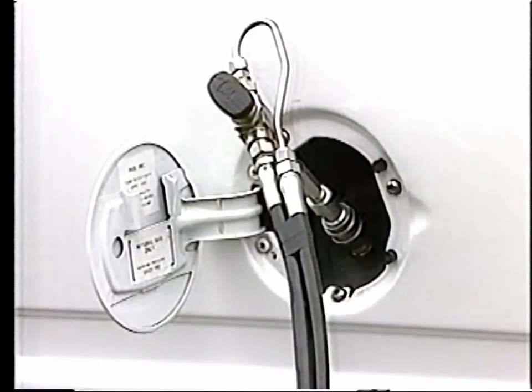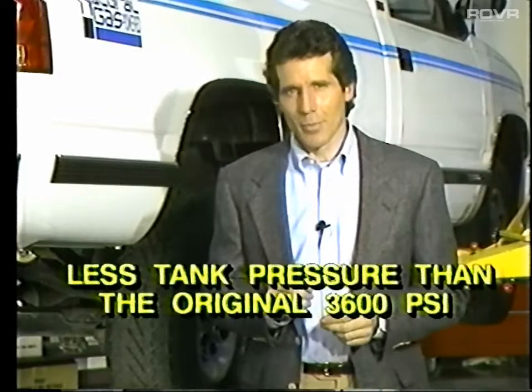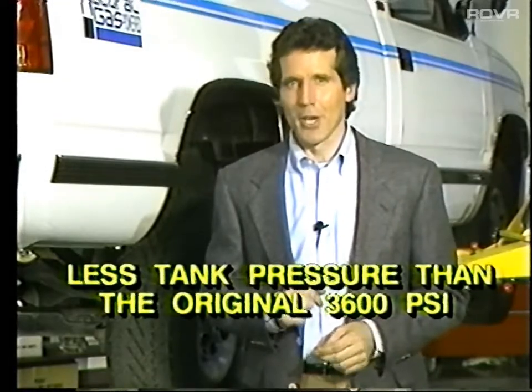If the truck's fuel tanks are filled using the fast fill method, the natural gas is forced into the tanks at a high flow rate. When this occurs, the gas is heated as it's forced through the valves. And as we all know, heated gas expands. And here's where the problem occurs. When the tank pressure hits 3,600 psi, the tanks appear to be filled and ready to go. But what happens? As the gas inside the tanks cools or stabilizes over a period of hours, it contracts, yielding considerably less tank pressure than the original 3,600 psi when the tank was filled, and thus providing less driving range than the 200 miles that should have been expected.